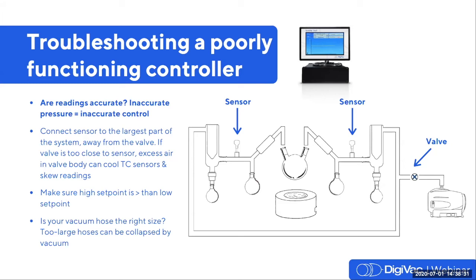Connect your sensor to the largest part of the system away from the valve. If the valve is too close to the sensor, excess air in the body of the valve that is released when it activates will briefly cool the thermocouple and cause erratic readings. Remember, all of our vacuum readings hang on what those heated filaments inside the sensor do. So the valve has been holding on to a bit of air that otherwise has been evacuated from parts of the system. And then when it opens up, a puff of that air will come out and instantly provide a bit of gas to temporarily cool those filaments inside, which can cause a reading that jumps up and down in time with the valve opening and closing.